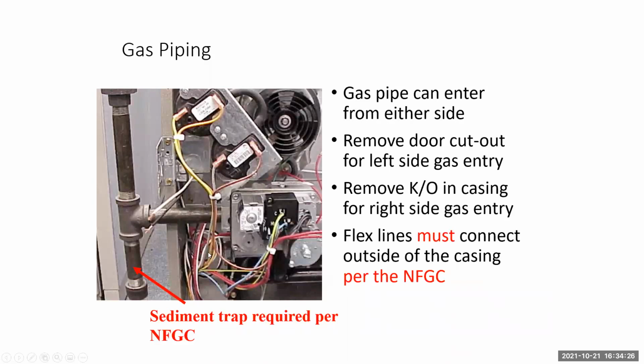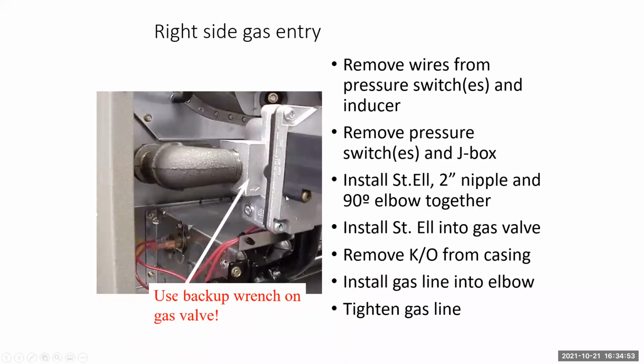Gas piping, we're allowed left and right side entrances on gas piping. No flex pipe connections inside the cabinet housing. If you're flex piping, everything's done externally. Sediment traps are required. Left side, it's pretty simple. I mean, knock out, straight in. Right side, the easiest way to pipe in off the right side entrance on gas is to get everything out of your way. Take your J box out, take your pressure switches out, get everything out of your way, get your gas line in there. As long as you do this right, there will be enough room.